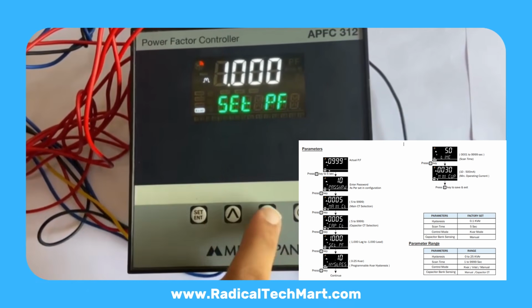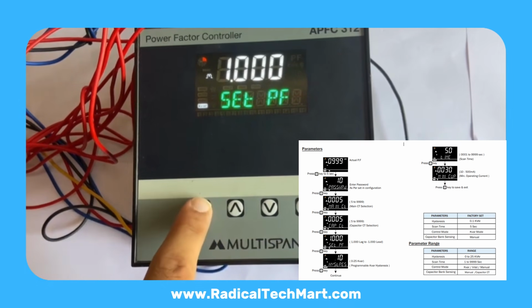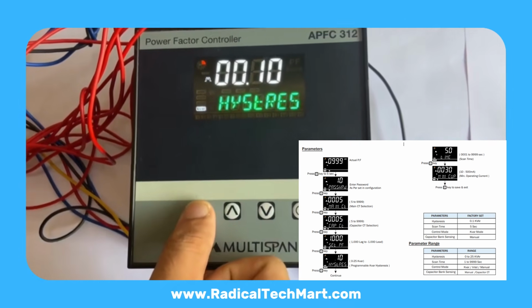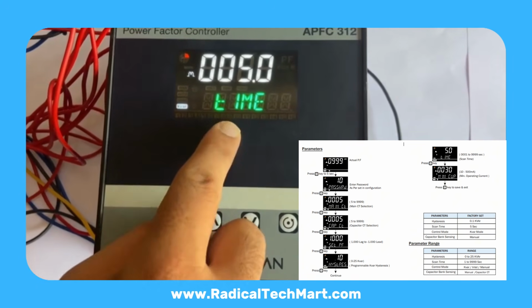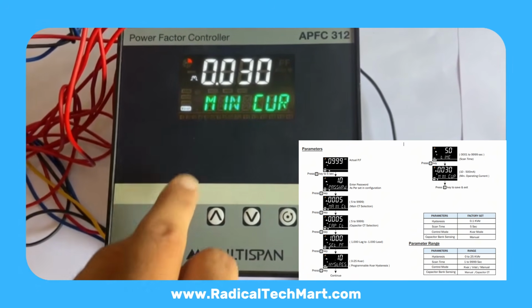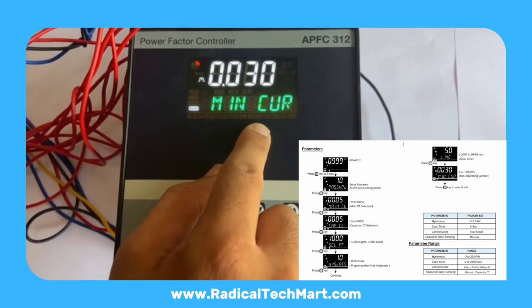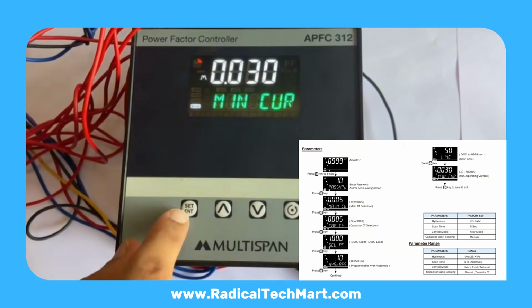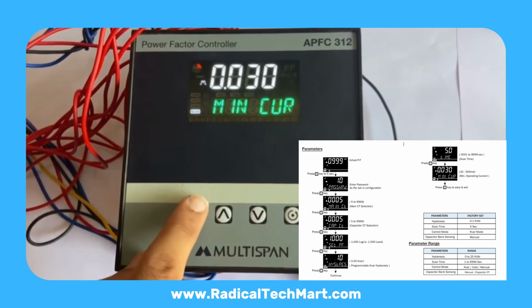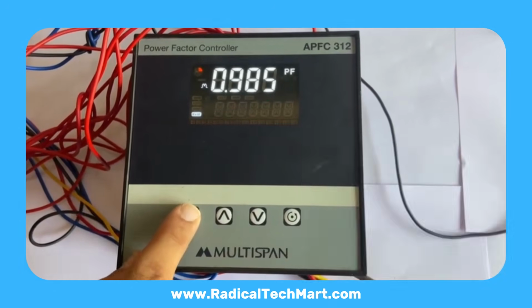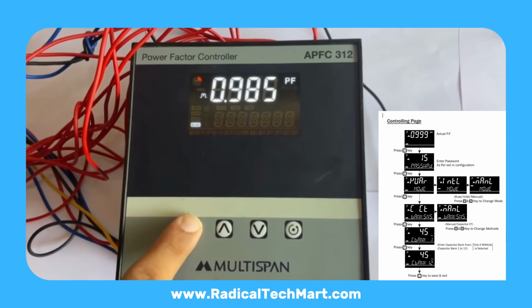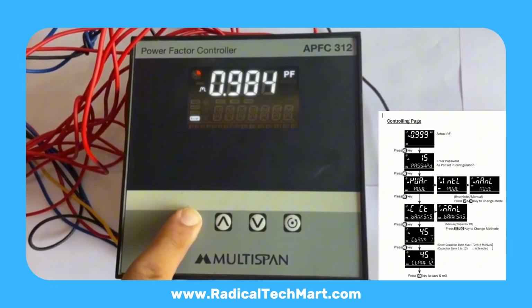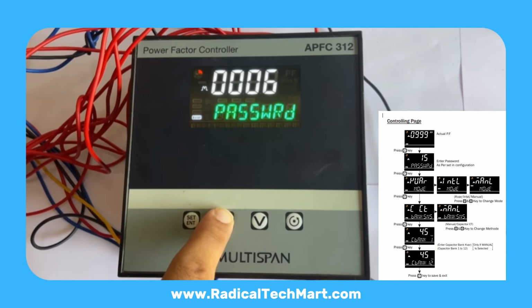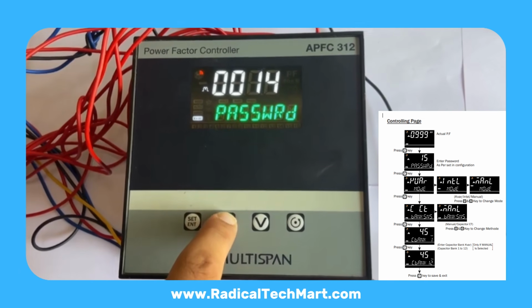Press set. The next parameter is the minimum current required for APFC switching. For example, if the secondary of your CT gets 30 milliamperes, the APFC relay will start operating. This prevents false switching when current is very low. Press set. To configure capacitor bank logic, press set until PASS appears. Enter the password 15. Press set.